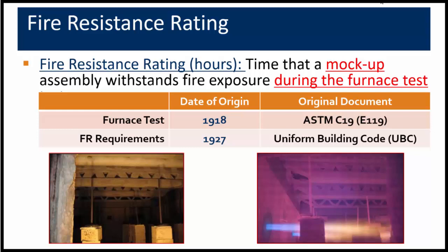Fire testing of building components in a furnace goes back almost 100 years. Requirements for fire resistance testing of building components date back to the 1927 edition of the Uniform Building Code. This method of fire testing has been criticized in recent years and was the subject of increased scrutiny following the collapse of the World Trade Center in 2001. The construction of fire resistant rated buildings is largely dependent upon the results derived from a 17 foot by 17 foot furnace, which cannot test components larger in size. It does not test connections, and it may not be related to the actual fire load of the building.